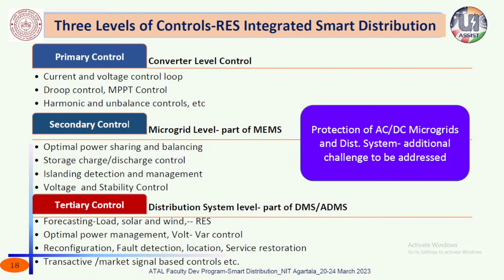So optimal charge-discharge control, islanding detection management, voltage stability control within the microgrid. Then if you have a microgrid and the rest of the distribution network, you have to operate all of them together optimally. That requires an energy management system, distribution management system, or advanced distribution management system, and that is tertiary control, requiring very accurate forecasting: renewable forecasting, load forecasting, power management, volt-var control, reconfiguration, fault detection, location.